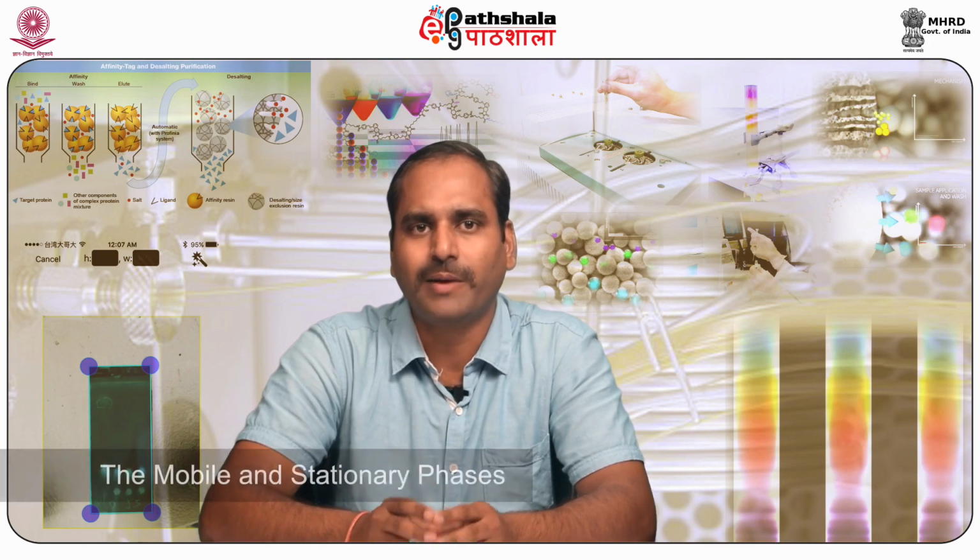The sample is injected into the heated injection port where it is volatilized and carried into the column by the carrier gas. The sample is separated inside the column, usually a long silica based column with small internal diameter. The sample separates by differential partition of the analyte between the mobile and stationary phases.